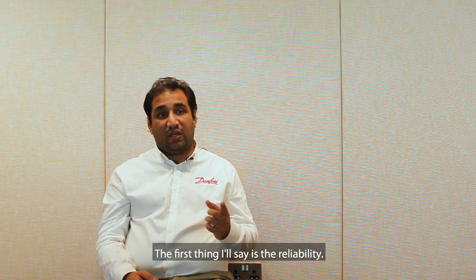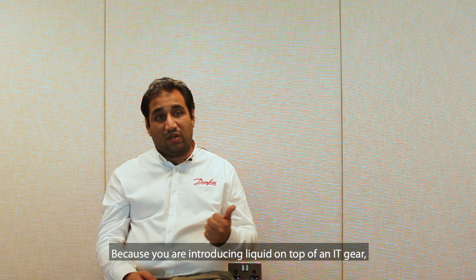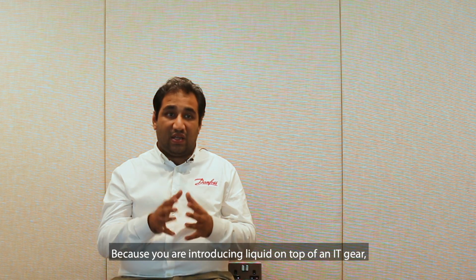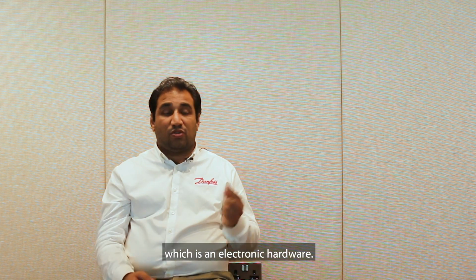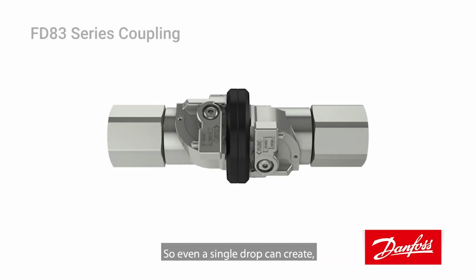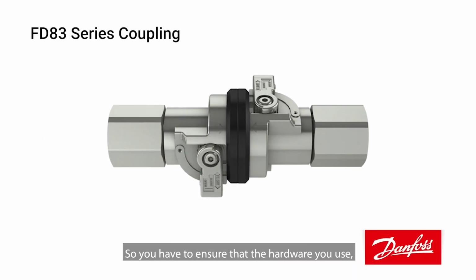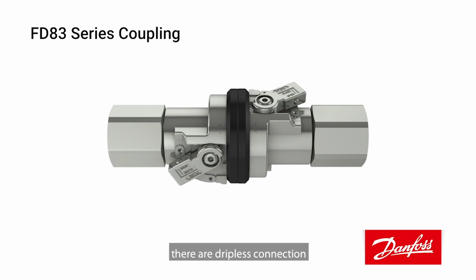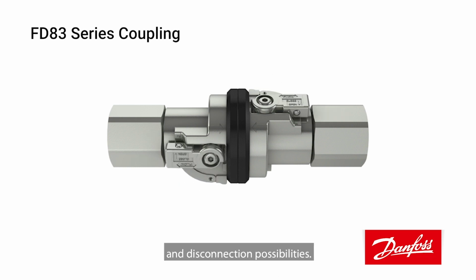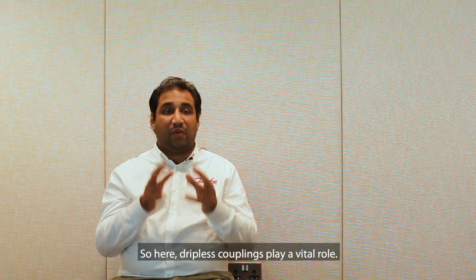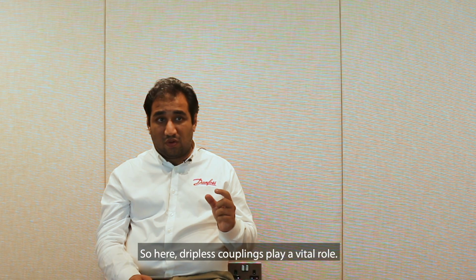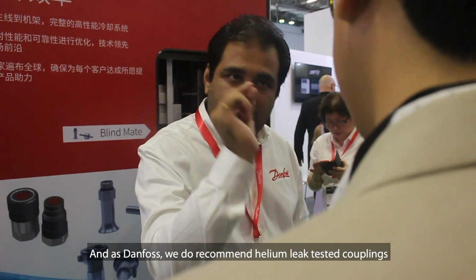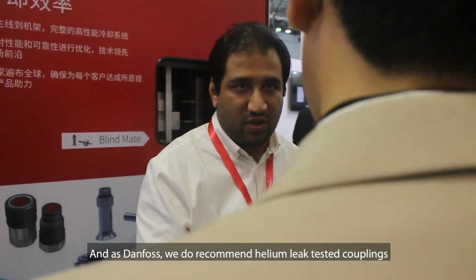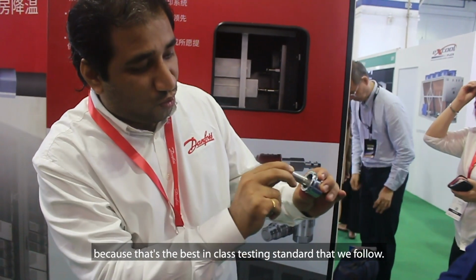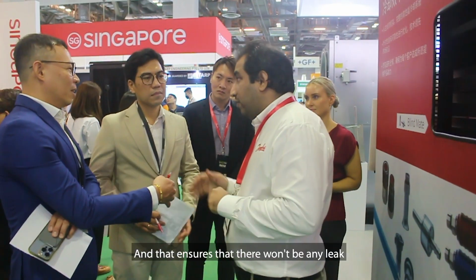The first thing I'll say is reliability, because you're introducing liquid on top of IT gear, electronic hardware, so even a single drop can create massive downtime. You have to ensure the hardware has dripless connection and disconnection possibilities, so dripless couplings play a vital role. At Danfoss we recommend helium leak tested couplings, the best-in-class testing standard we follow, ensuring there won't be any leak at any given point in time.